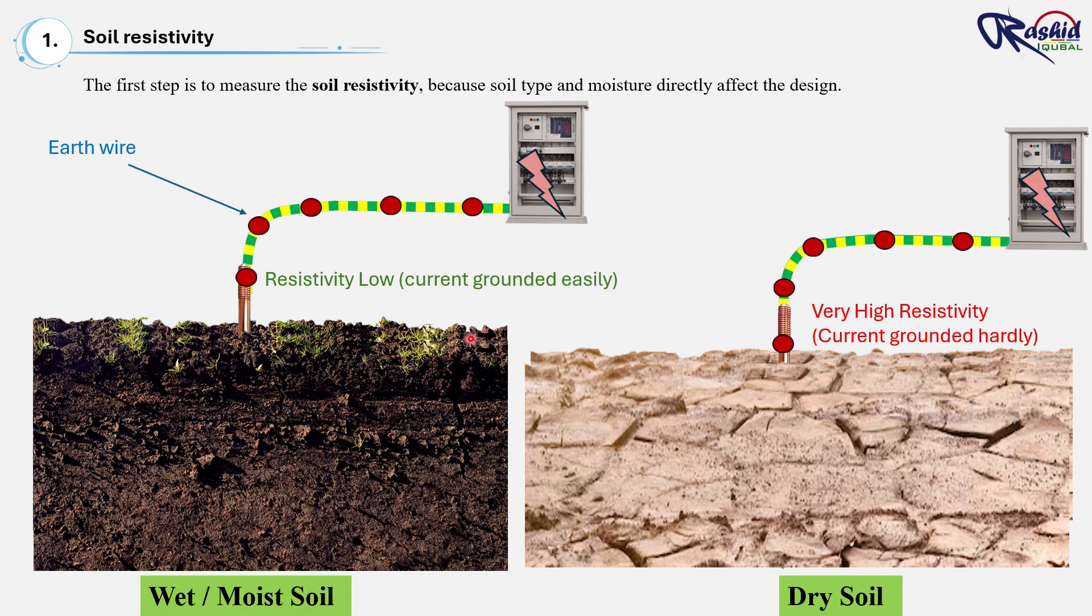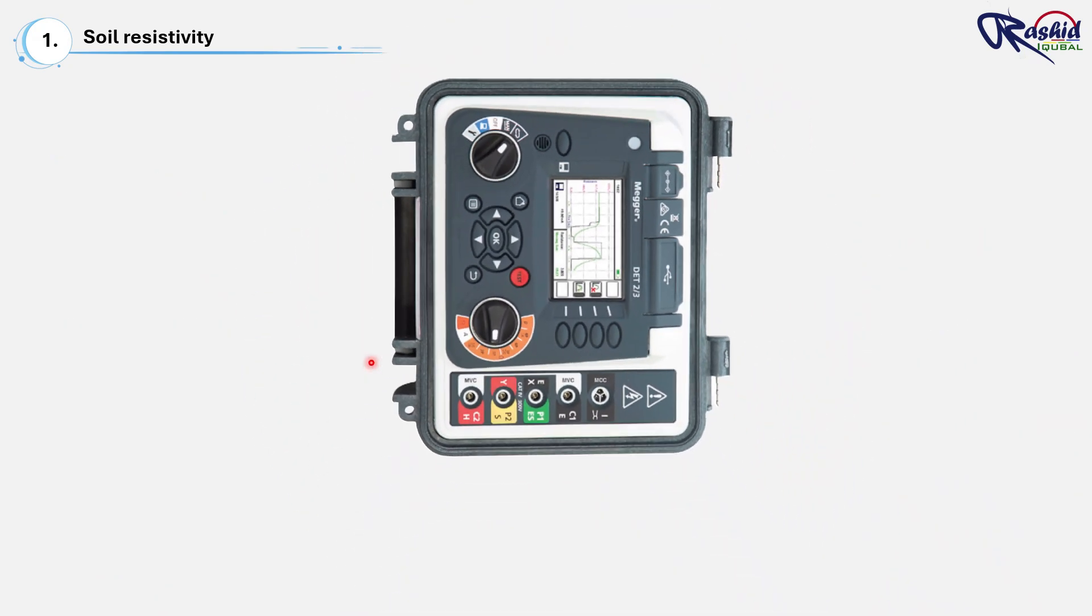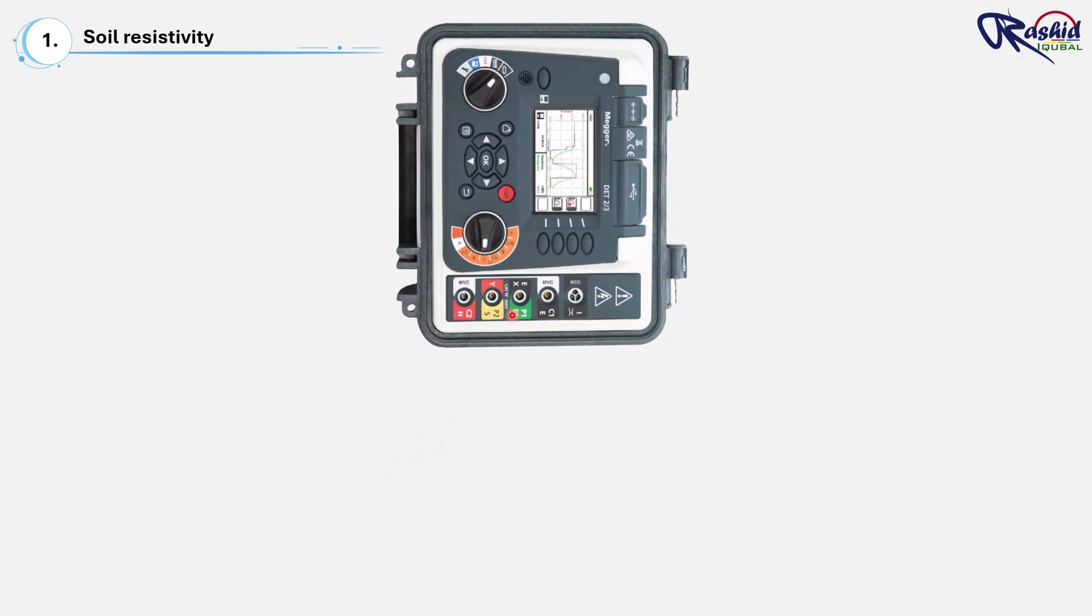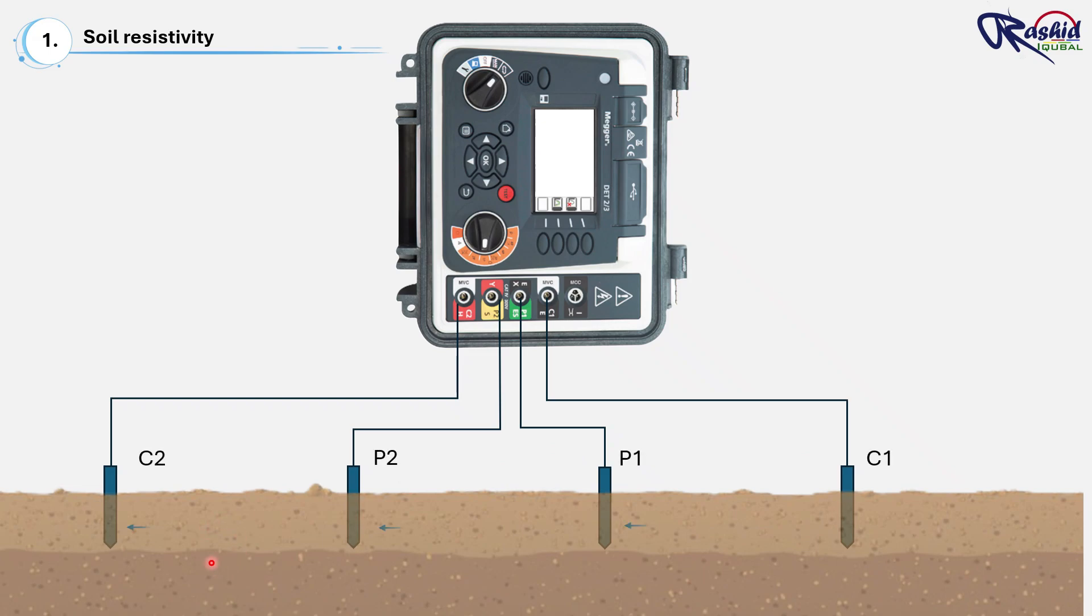To find out the actual soil condition and resistivity, we use a standard method called Wenner four-point test. In this method, an earth resistivity meter is used to perform tests. Drive four small test probes into the soil along a straight line and maintain equal spacing. Inject current between the outer two probes, that is C1 and C2, as you can see here.